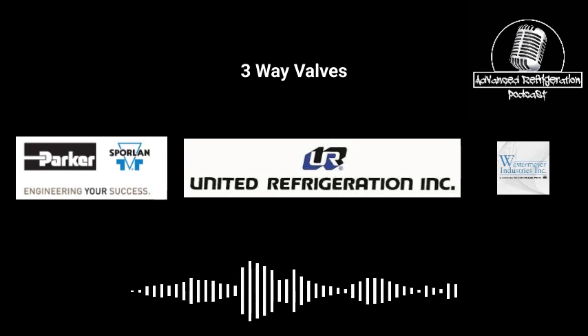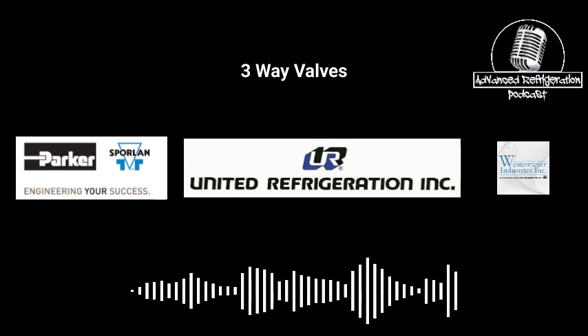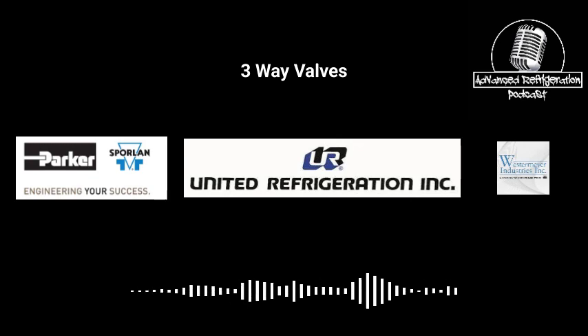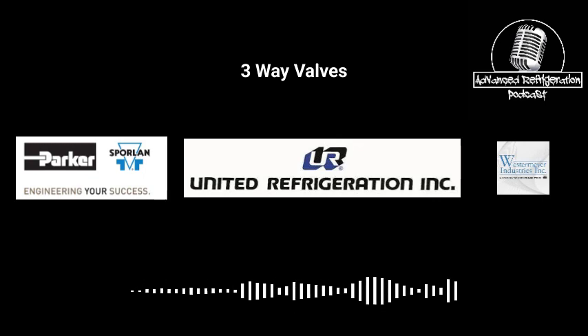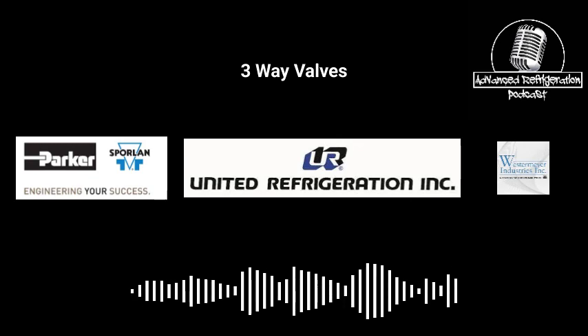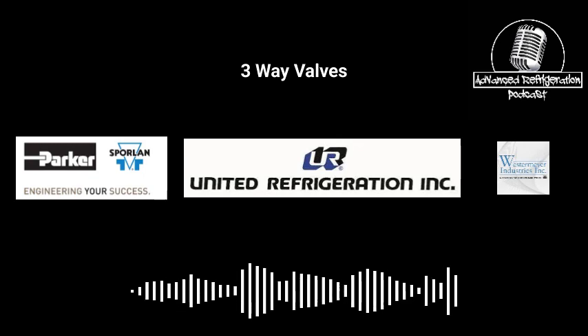Some of the Sporlan valves, the split condensers and the heat reclaim valves, will have a B port in there. Any Sporlan three-way valve you see with a B port means it has a pump out equipped with it. Meaning it's pumping out that shut off side through the suction, so the pilot assembly where it vents out is also pumping out that side. Now be mindful when you use one of these B ports in a split condenser application, it takes a while to pump out. It's not a huge orifice that it's going through to pump out, so give it some time. But a B port does pump out.